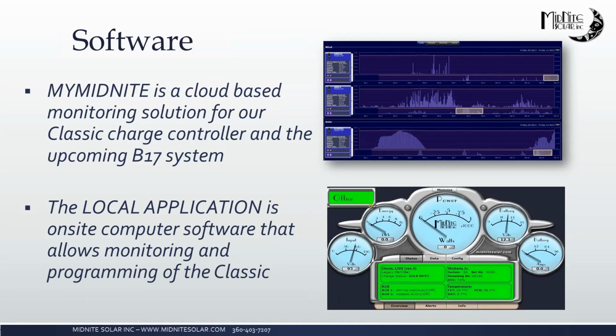You can go on there and expand that little white box out and say, okay, well, I see that we were going to float every day at 11 o'clock, and then on February 13th, you plugged in something because we never went to float again after that. And I'm seeing that we didn't even really get to absorb after that. So what did you plug in? It might just save you a trip to the site. It might help you understand. And it's also extremely useful just for the customer to be able to see at a glance. There's 12 to 14 items you can see on there, everything from state of charge to FET temperature to battery voltage, just a wide variety of stuff.